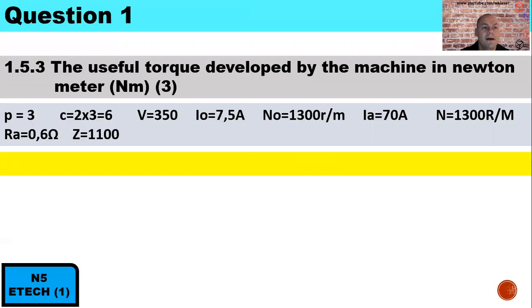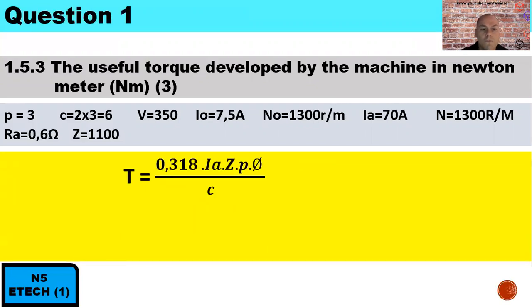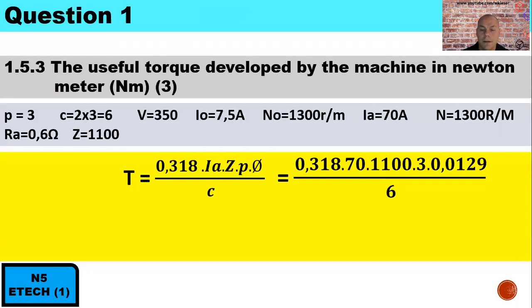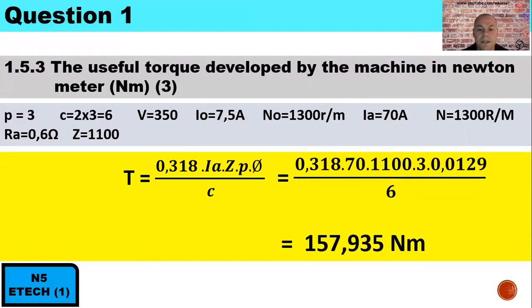Question 1.5.3: Calculate the useful torque developed by the machine in Newton metres. The torque formula is 0.318 × IA × Z × P × flux per pole, all divided by C. That is 0.318 × 70 × 1,100 × 3 × 0.0129 ÷ 6 (lap wound, 6 parallel paths). Therefore, the torque developed is 157.935 Newton metres.